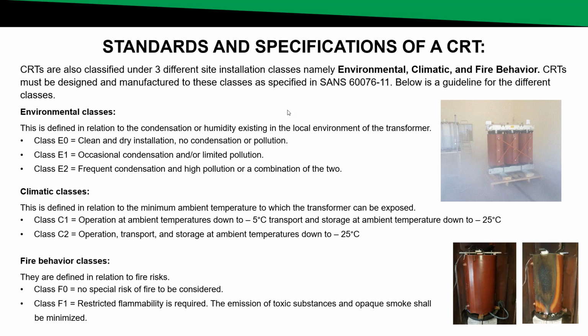The environmental class. The environmental class is defined by the environment the transformer is expected to operate in. For example, class E0 is clean and dry installation, no condensation or pollution. This would be typically an indoor installation where the transformer room or enclosure is kept very clean and tidy, and there is no condensation or moisture present around the transformer.